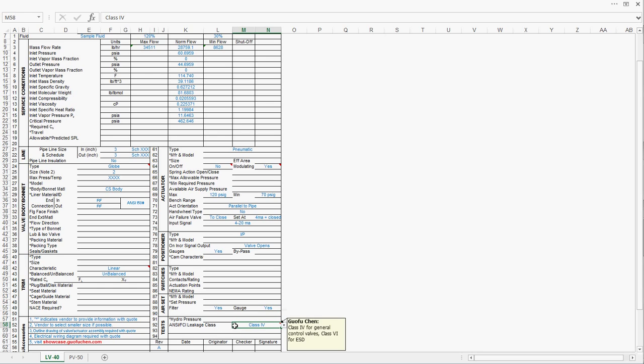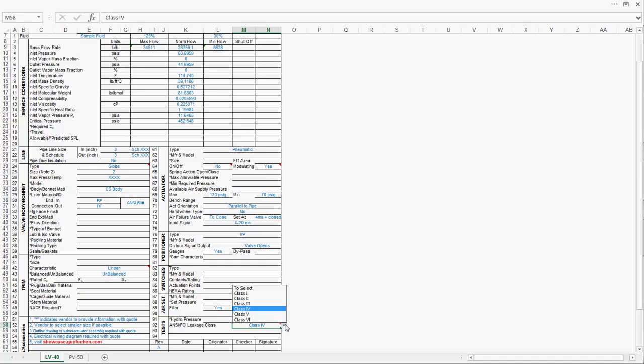Regarding the leakage of the valve, normally, a class 4 is sufficient. There are generally six types of leakage. Class 6 might be good for ESD emergency shutdown valve, but for most of the control valve, class 4 is good enough.